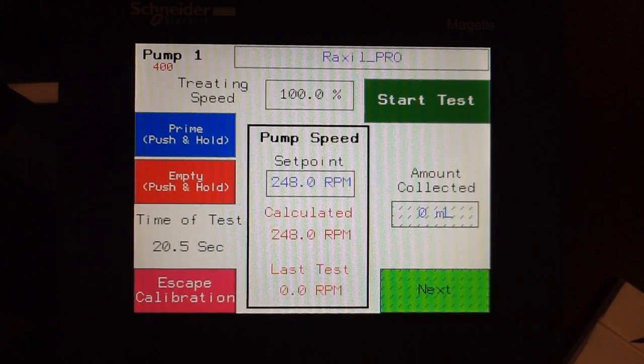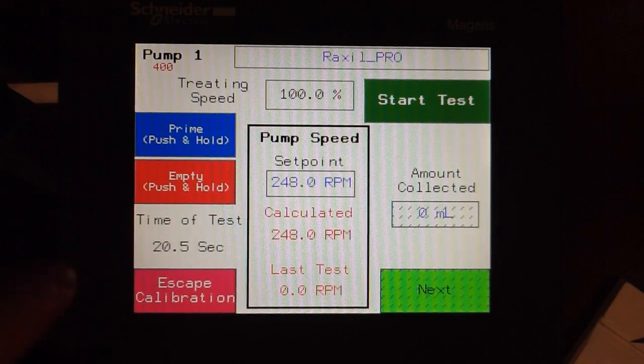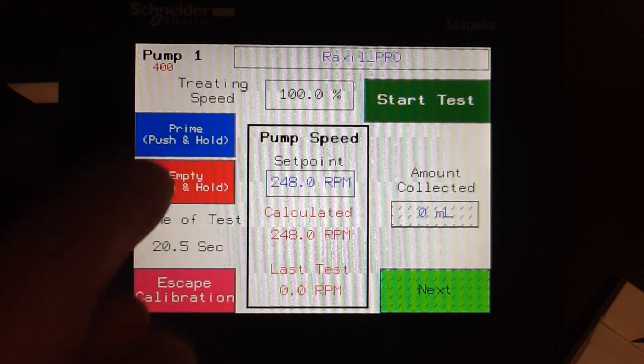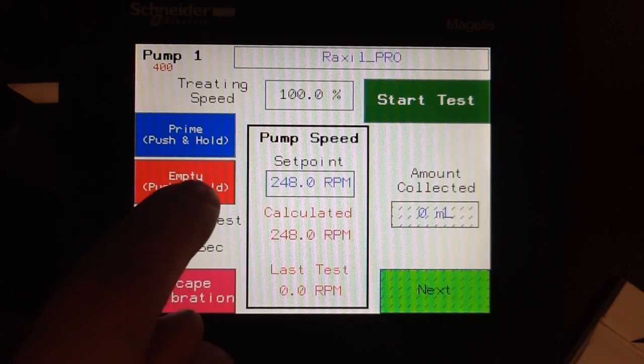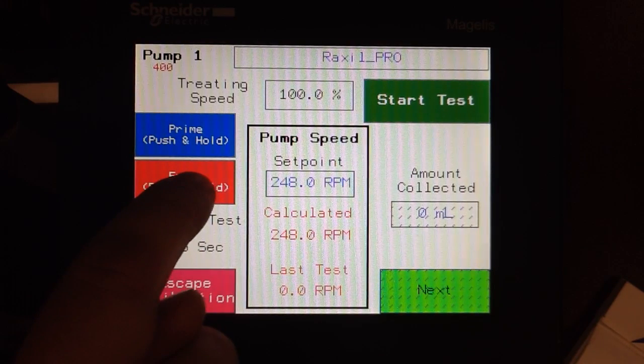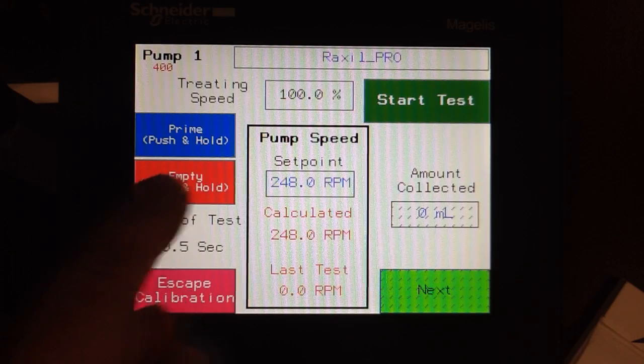To check calibration, we are simply going to touch the Prime button. Hold Prime until all of the air is out of the calibration cylinder. Next, touch Empty, and empty to the zero mark of the calibration cylinder. And then select Start Test.